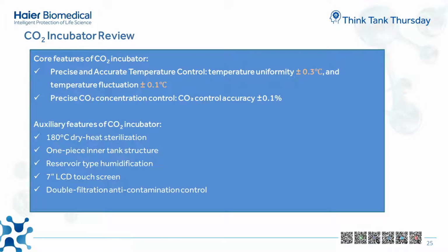So let's get a quick review of the biomedical incubators. From those important factors, first of all, the optimal cell growth: temperature uniformity, CO2 concentration and humidity. We have the accuracy level as shown in the list, and also contamination control. We applied the 180 Celsius degree dry heat sterilization methodology, and the structure is designed with a one-piece inner tank. Also, the humidification is concentrated in the cold spot in the rear part of the chamber, so the condensation will be returning to the reservoir.